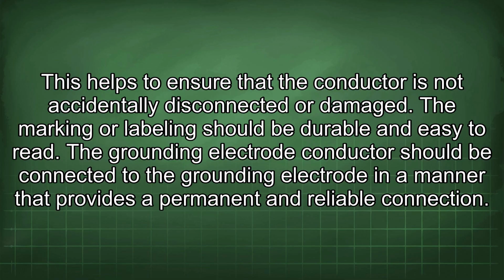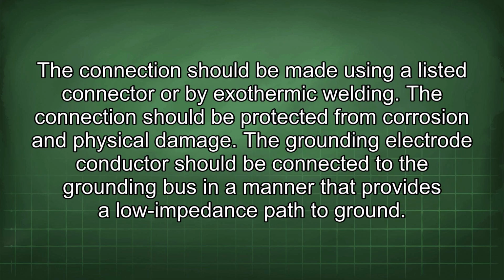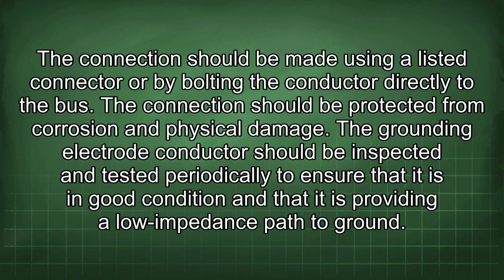The grounding electrode conductor should be connected to the grounding electrode in a manner that provides a permanent and reliable connection. The connection should be made using a listed connector or by exothermic welding. The connection should be protected from corrosion and physical damage. The grounding electrode conductor should be connected to the grounding bus in a manner that provides a low impedance path to ground. The connection should be made using a listed connector or by bolting the conductor directly to the bus. The connection should be protected from corrosion and physical damage.